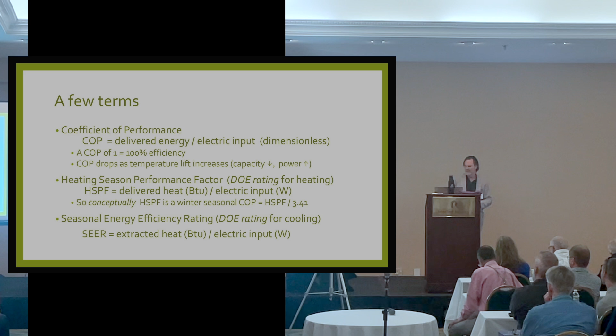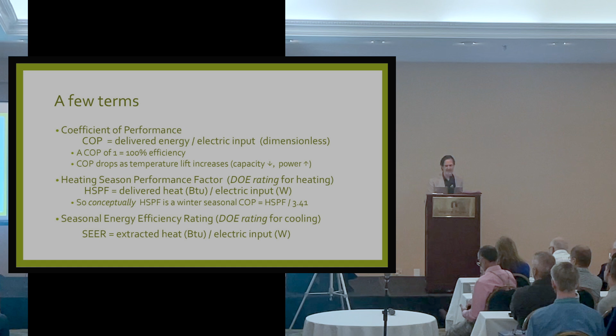It's the delivered heat divided by the electric input, but it's in BTUs per watt. So it's not the same scale as a COP. It's equivalent, but if you looked at an HSPF as a number, you might have 8.5 or 9 or 10. That's 3.4 times what the seasonal COP would be, because that's the number of BTUs in a watt, right? It's 3.41. So you can kind of do a crosswalk between the 2 metrics, but it's important to remember that HSPF is a rating. It's a very specific test procedure that leads to an HSPF, and it doesn't necessarily represent how the system works in real life.